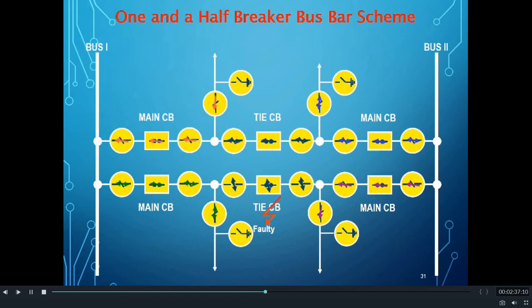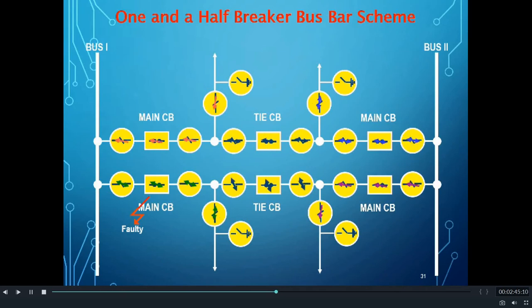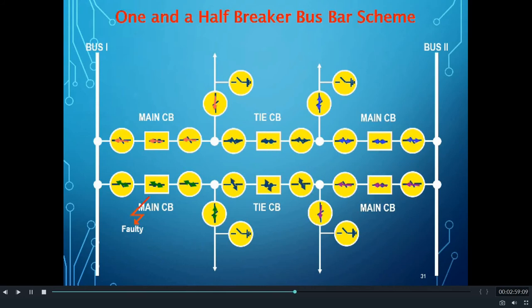Similarly, when there is a fault in a main CB, the main CB trips, but none of the feeders will be affected. The feeder gets disconnected from one bus on one side, but from the other side it remains connected through the tie CB. Hence, because of any circuit breaker fault, the system will not be affected.